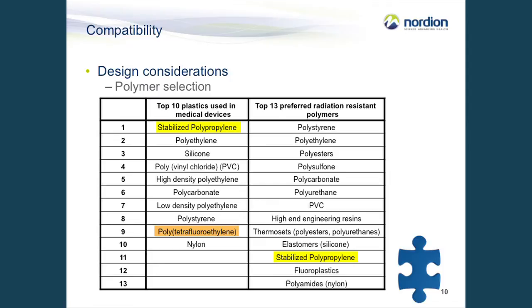This table shows the polymers that are most commonly used in medical devices and also which polymers are preferred from the standpoint of radiation resistance. Note that the most commonly used polypropylene when radiation stabilized is considered gamma stable. And in fact, almost all of the commonly used polymers can be found in the radiation resistant column. Some materials such as PTFE have poorer radiation resistance, but can still be gamma sterilized depending on the dose and application. You need to look at whether or not the degradation affects the performance in the intended use. And I know that Teflon is irradiated today.